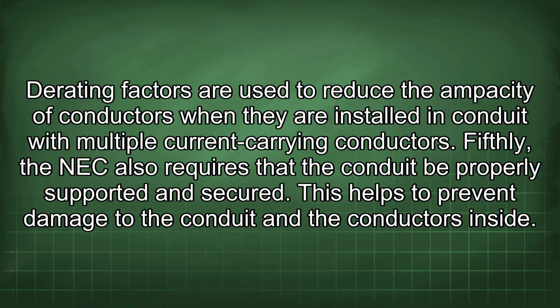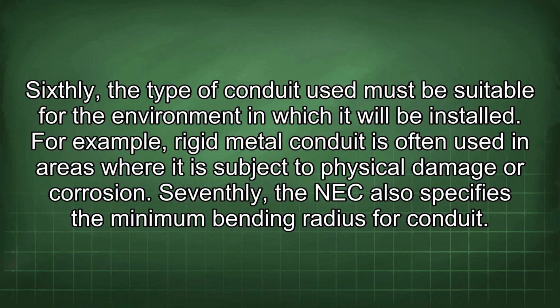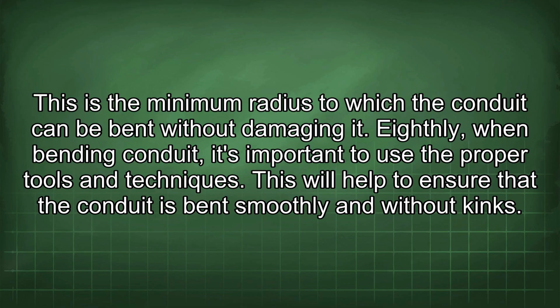Fifthly, the NEC also requires that the conduit be properly supported and secured. This helps to prevent damage to the conduit and the conductors inside. Sixthly, the type of conduit used must be suitable for the environment in which it will be installed. For example, rigid metal conduit is often used in areas where it is subject to physical damage or corrosion. Seventhly, the NEC also specifies the minimum bending radius for conduit. This is the minimum radius to which the conduit can be bent without damaging it.